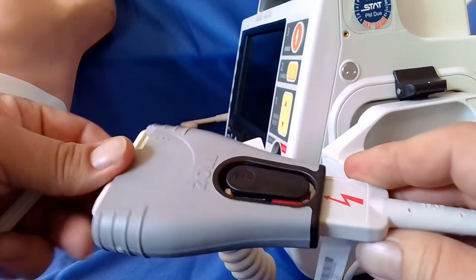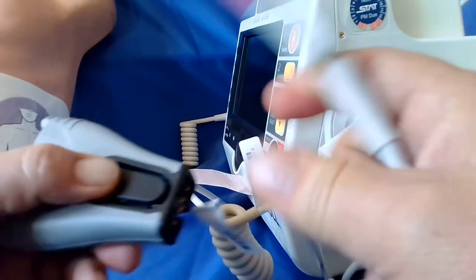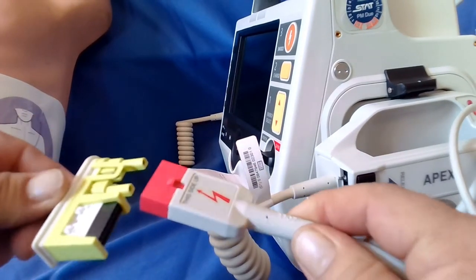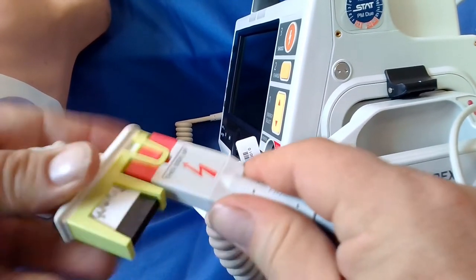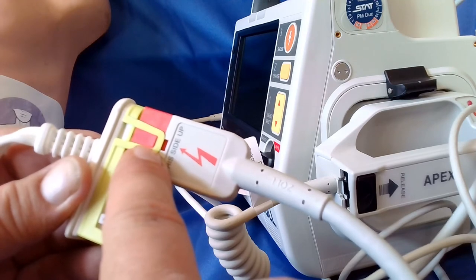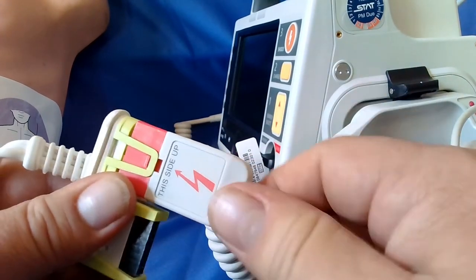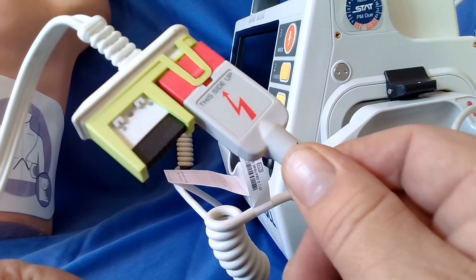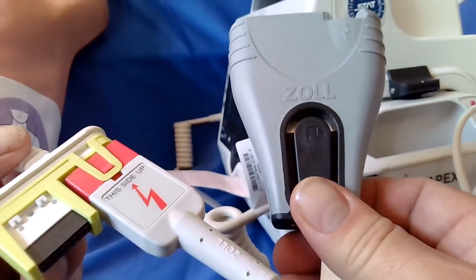Should for some reason you lose this puck, you can still use the pads and connect it to your device by just separating it into that section on the cable and making sure that connector now sits and is connected to the pads correctly and is in firm, and in no way is this easily going to detach from the cable.